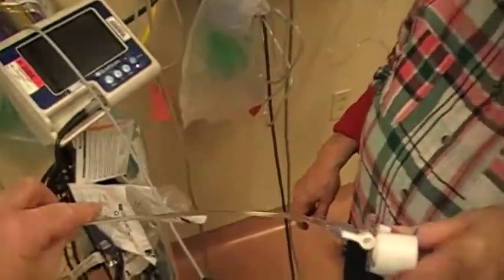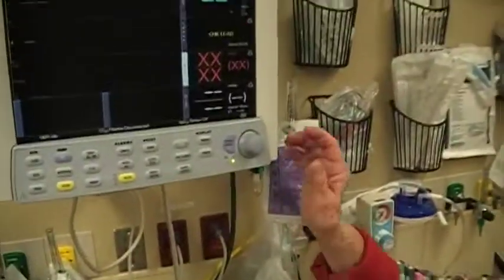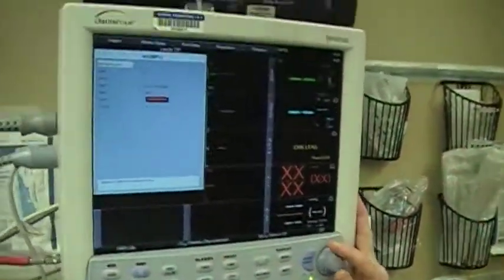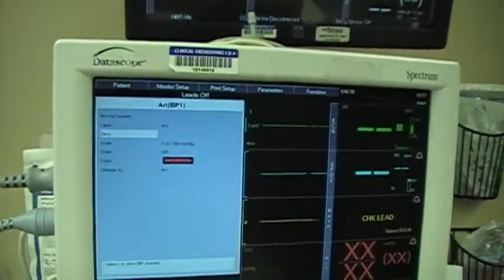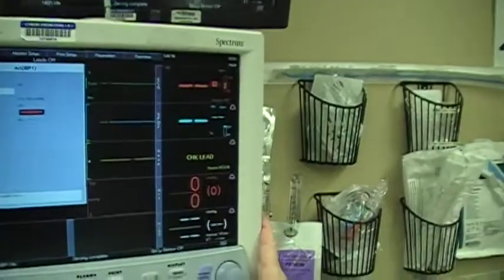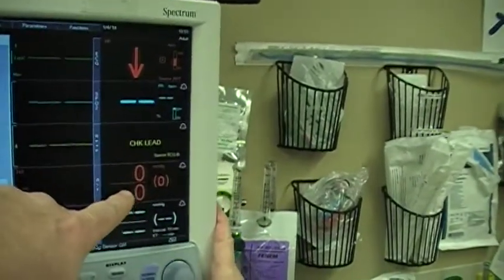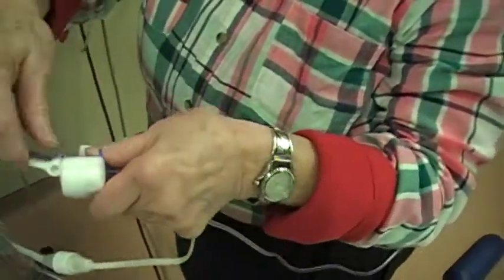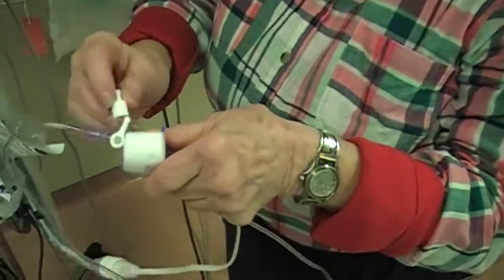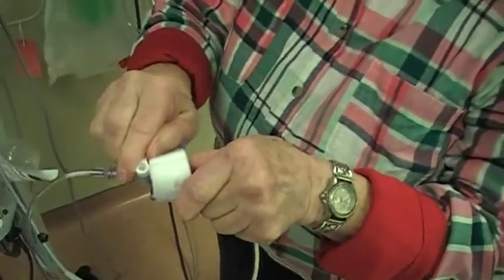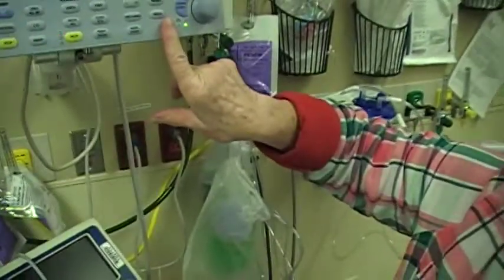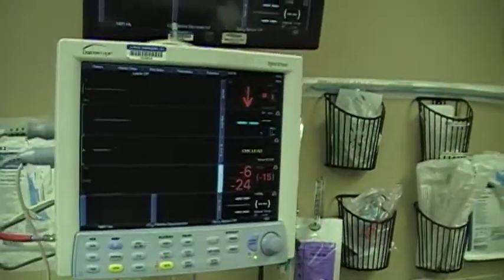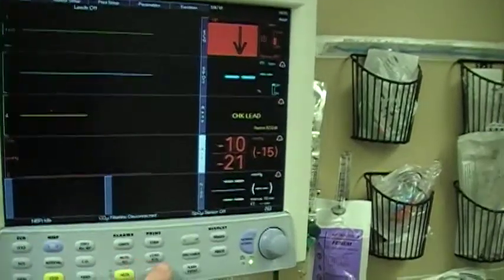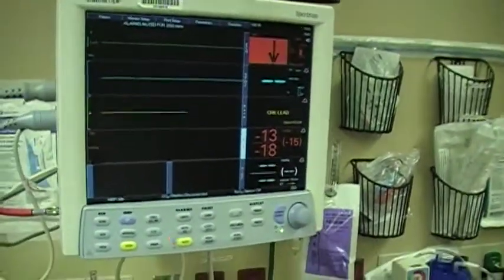So now that it is basically closed off to the patient side and open to atmospheric pressure, go ahead and hit that again. She's going to scroll back down to 0. And then go ahead and hit the button and it will 0. Wait for it, and you can see that now it says 0/0 instead of X. At that point, you can go ahead and close that again, straight up and down, and reapply that cap, make sure you maintain aseptic technique. We can go back and hit main screen or normal screen, and you'll notice that you have an arterial waveform already on your monitor and ready to go.